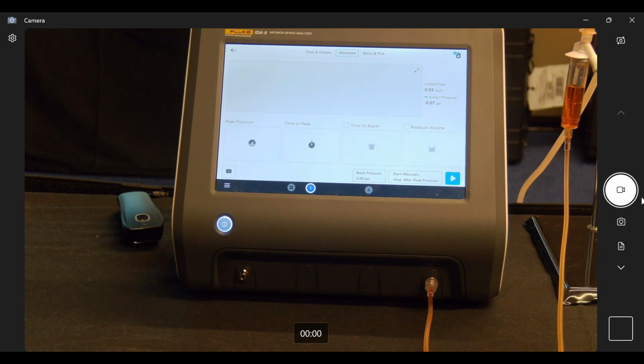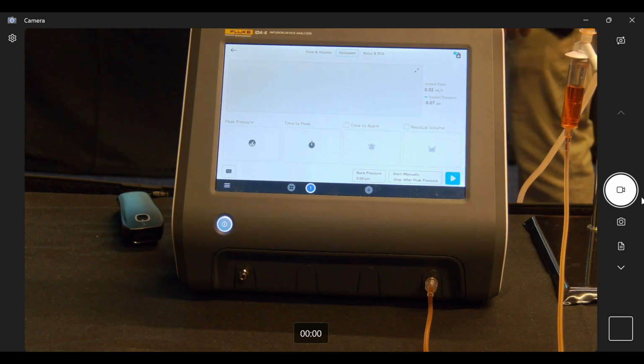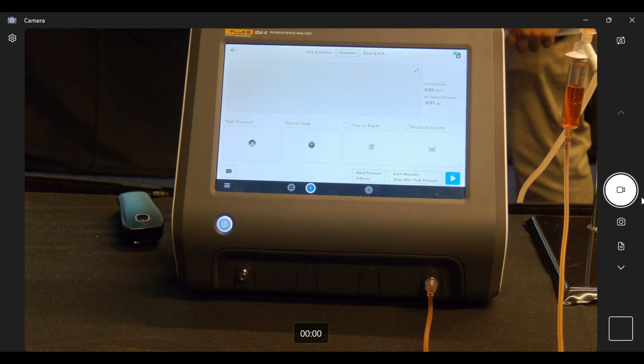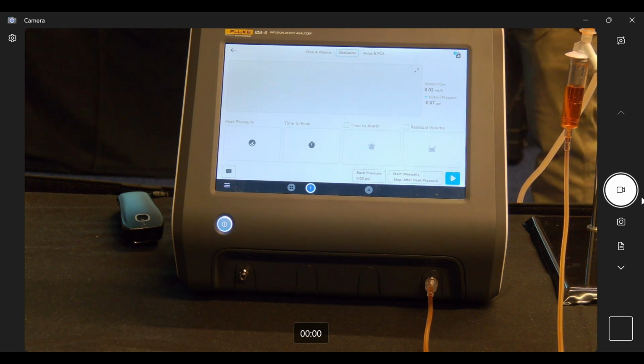Does anybody even use the calibrated pressure, or calibrated flow cassettes anymore? Because they were really hard to find when COVID happened. So people were just grabbing general test sets off the floor. Managers, go look at your shop and see what they're doing, because you'll probably find out they're not using the calibrated test sets because they're really expensive and you're only supposed to use them for 20 pumps, and then you throw them away and get another test set. Just saying.